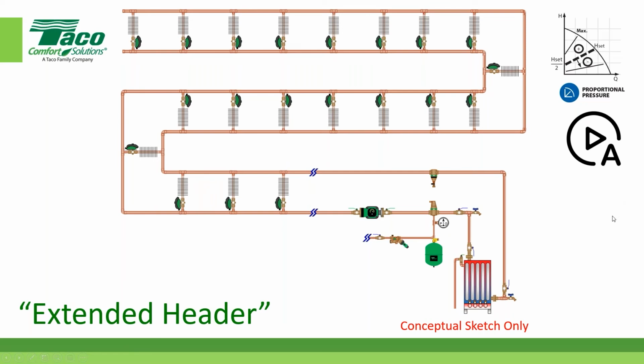Now, with that in mind, you have to recognize the fact that this circulator right here is going to be affected by all of this supply and return piping, right? So let's give you a scenario. We had a design condition during the night, and now it's becoming daylight and it's clear skies. It's cold out, but the sun's coming up, and it's got solar gain on the east side of the building, which it's facing, okay? And now every other one of these zones starts to close, okay? Well, if I have the circulator in the appropriate mode, the circulator is going to feel those zones closing, and what's it going to do? It's going to slow down.